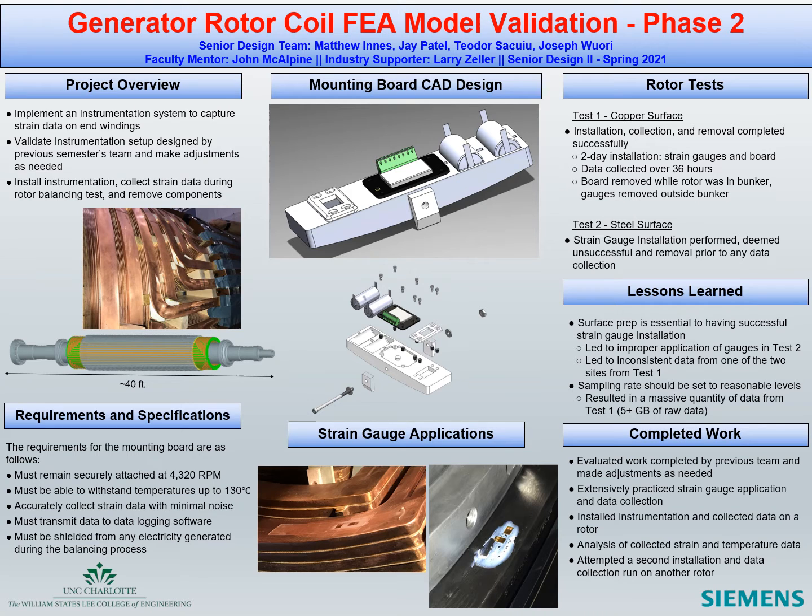Welcome to the Siemens FEA Phase 2 poster presentation. This project builds upon the work completed by the UNCC senior design team during Phase 1. The project arose from the need to validate stresses on the copper windings of a rotor on a utility scale generator. The goal of this project is to collect strain data from the copper windings and compare that data with existing FEA model data developed by Siemens.